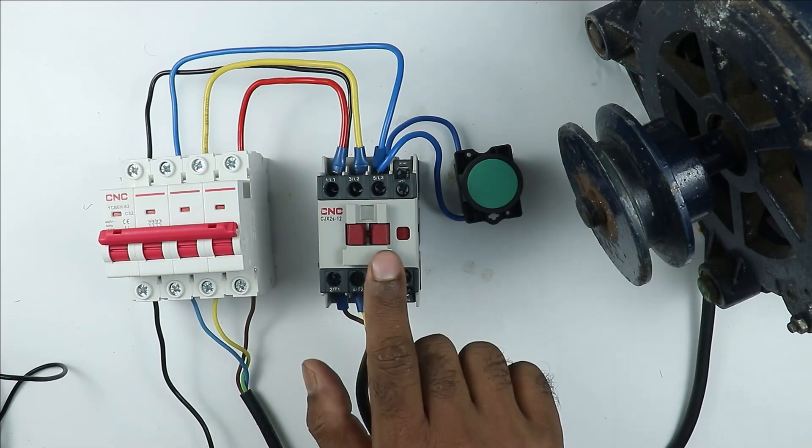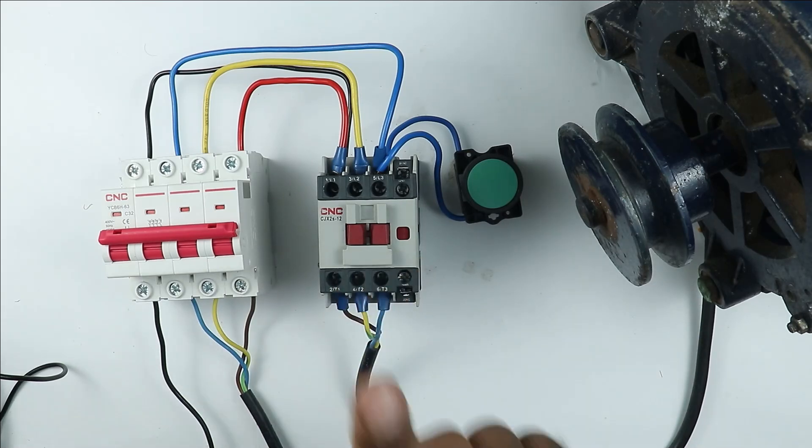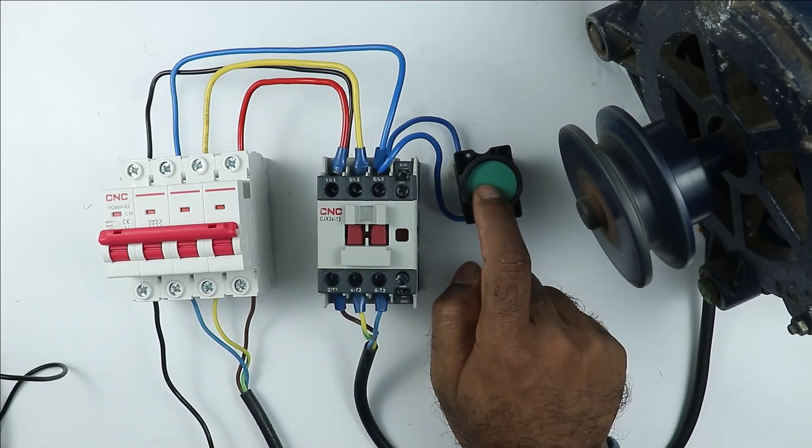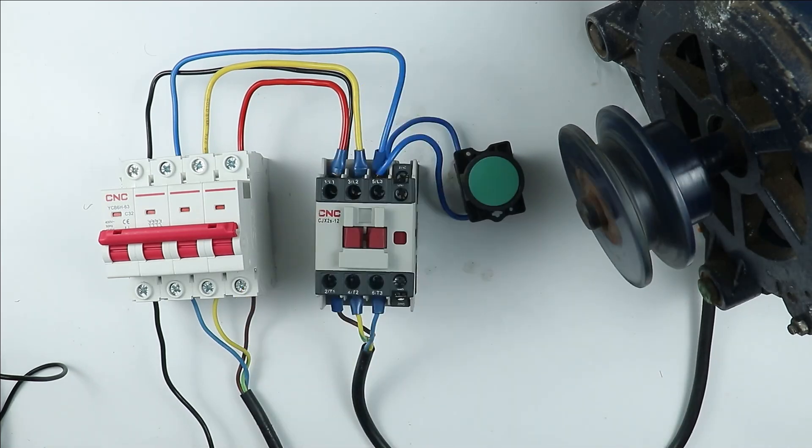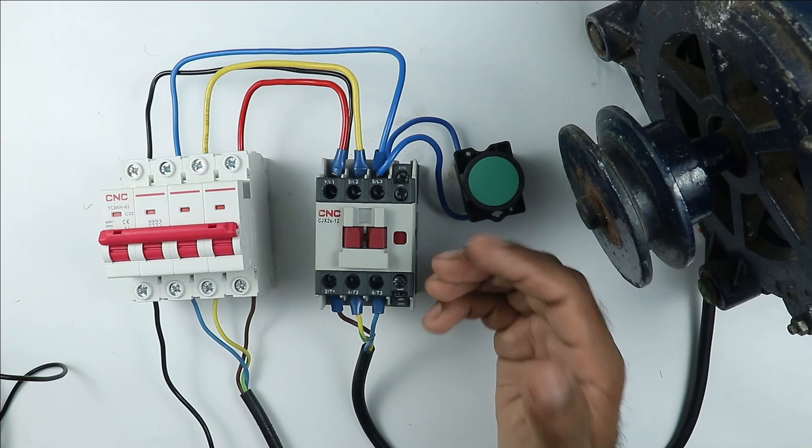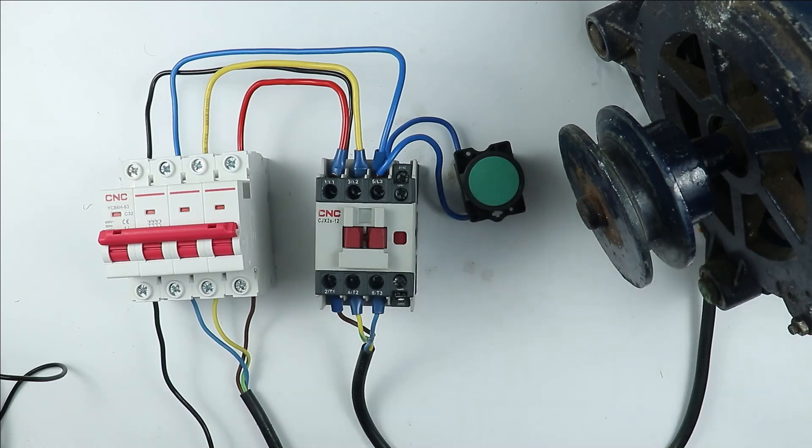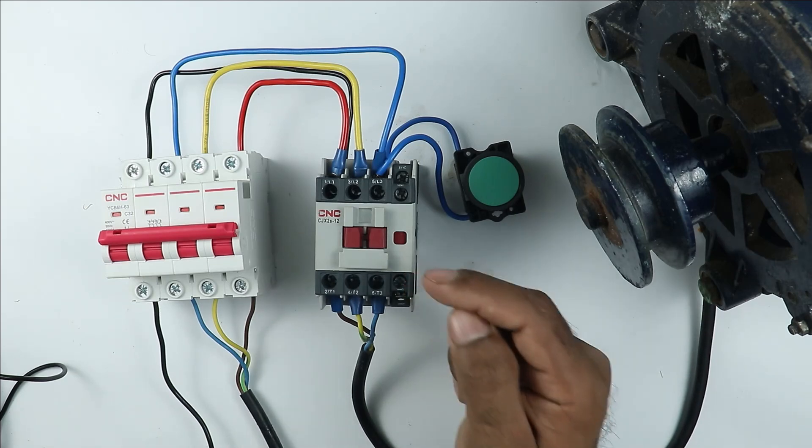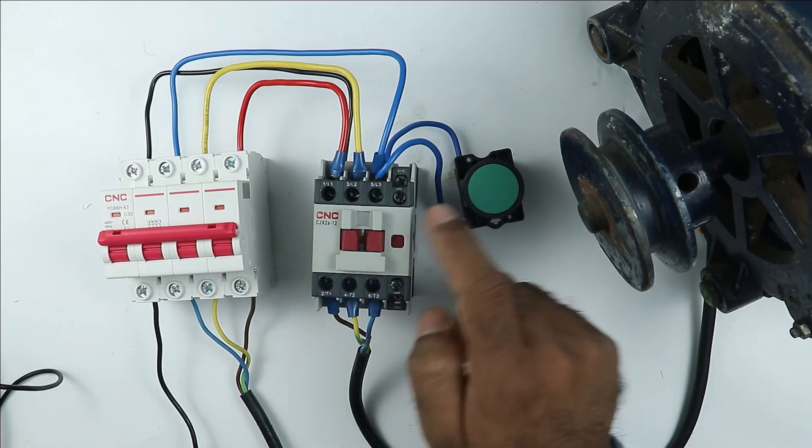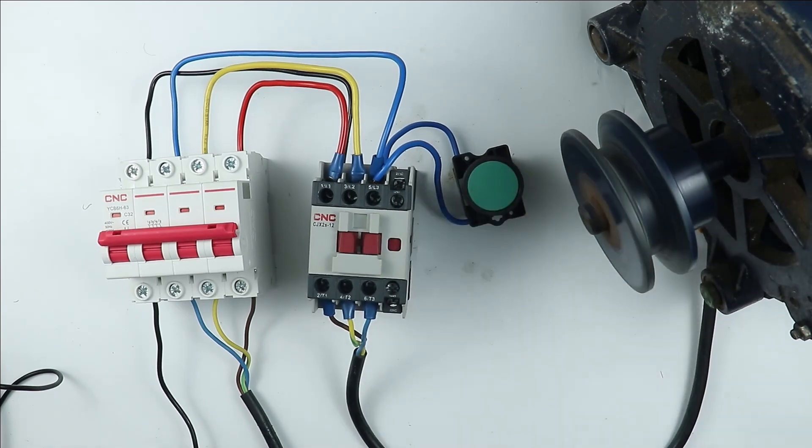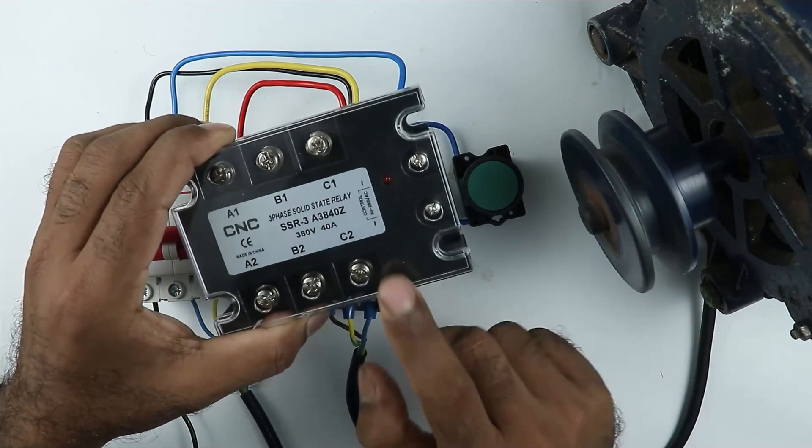As I told you when using this contactor when we turn this on sparking is generated. Now if you place this contactor in hazardous area means you want to use this where chances of catching fire is more, then in that condition this will catch fire because sparking is generated. So in any hazardous area if you want to turn on and off a load then you have to use this type of solid state relay.